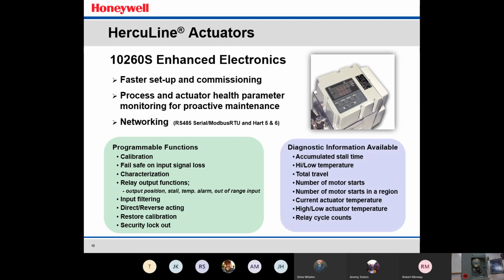The other feature that the smart electronics allows is a lot of diagnostic information. So say, for example, the actuator had been stalled out in the field, but walking up to the actuator without the smart electronics, you really don't know how long it was stalled. There is an accumulated stall time diagnostic, which gives enhanced information to allow you to troubleshoot the PID loop. High and low temperature, so it monitors the highest temperature the actuator has seen out in the field. So if you get into some conditions in the middle of the summertime, and this is right next to a blast furnace, and they're injecting 300-degree ambient temperatures and wondering why the actuator is failing, well, this will help store that for you.